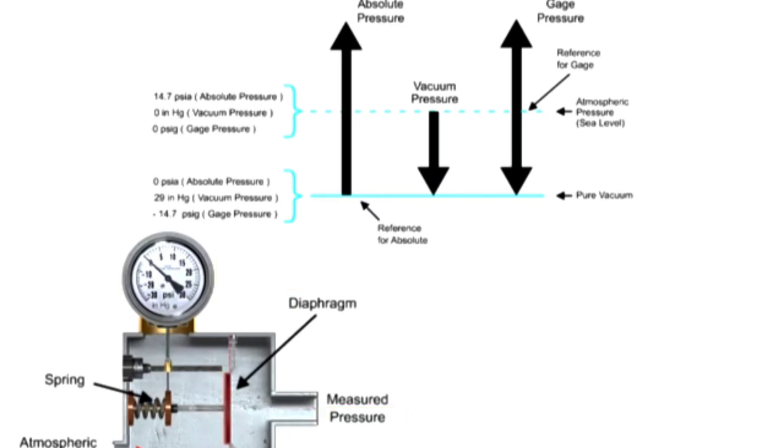Negative gauge pressures are indicated on the gauge with pressures below atmospheric pressure. Maximum negative value for gauge pressure is pure vacuum, or negative 14.7 PSIG.